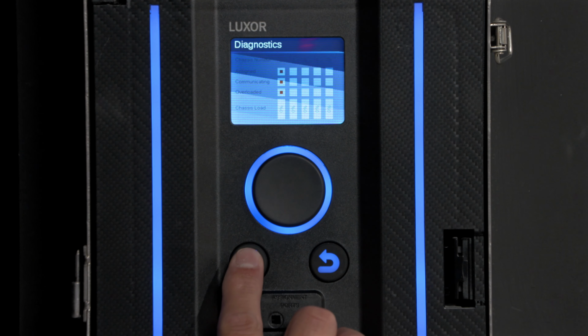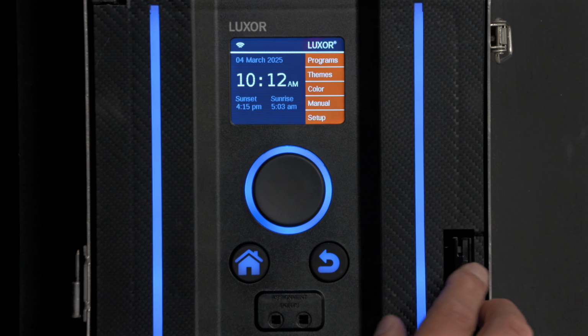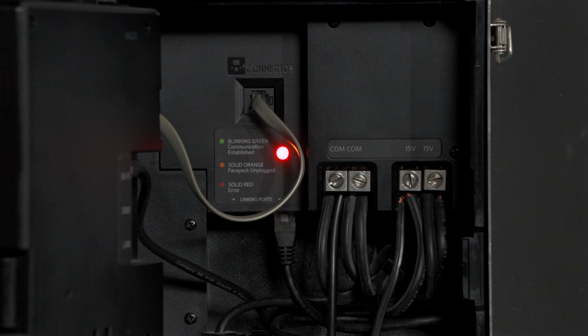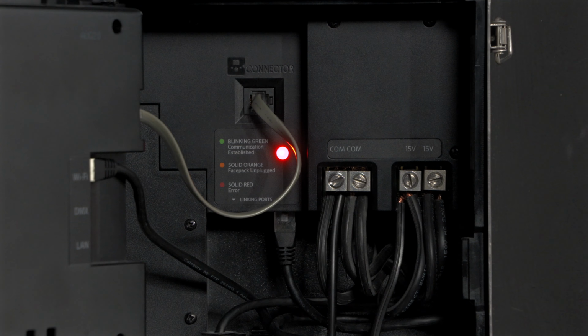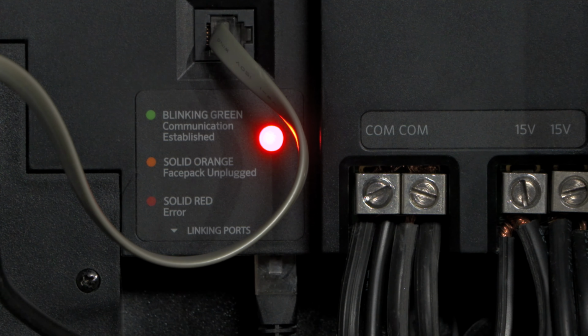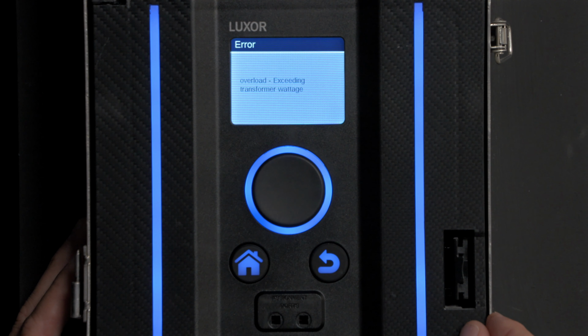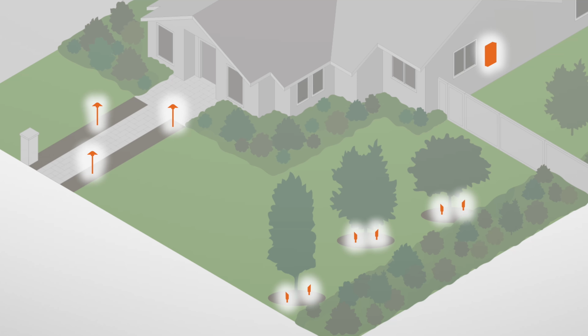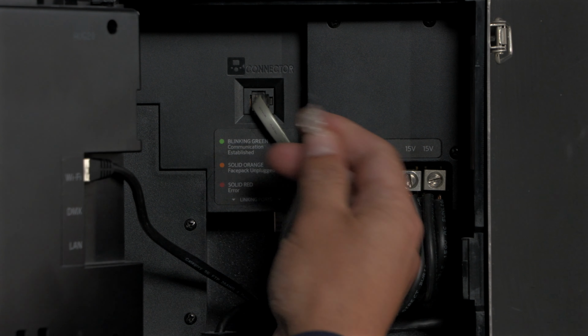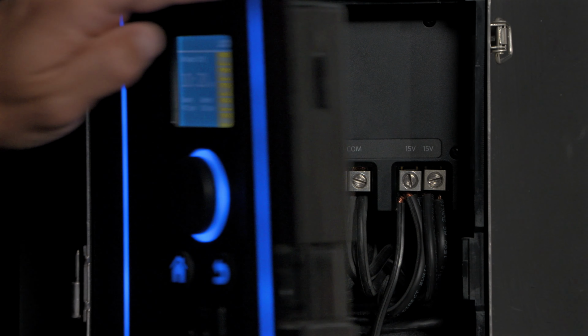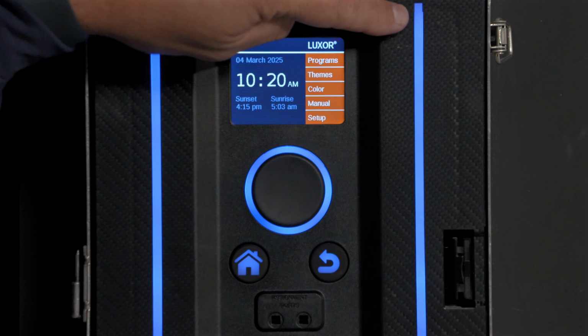The other way to tell if you have an overload is to open the facepack. And inside, the chassis LED will not be blinking green, instead it will be red. The way to fix this is to reduce the number of fixtures on the transformer. First, unplug the facepack to cycle power. You can confirm that the error message is gone after waiting a few seconds.